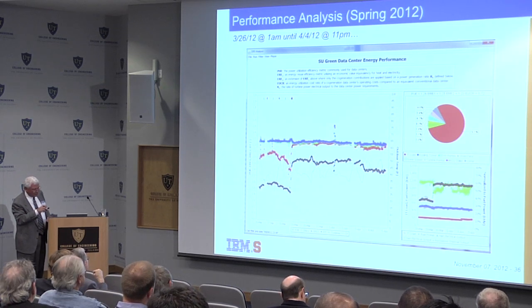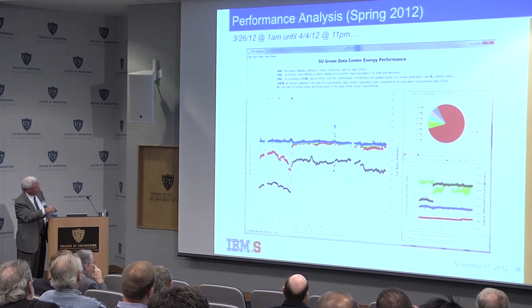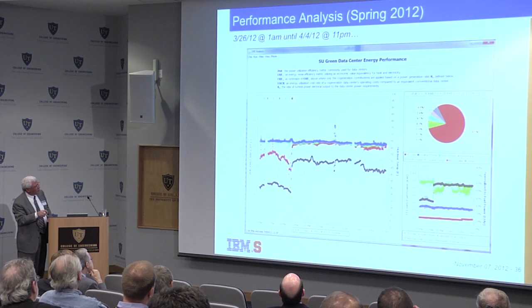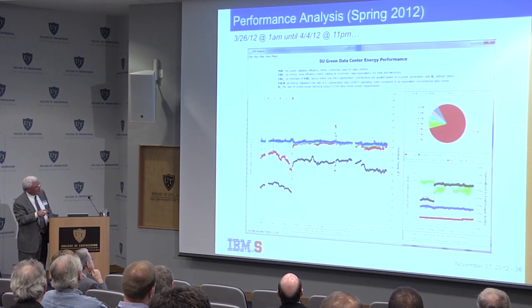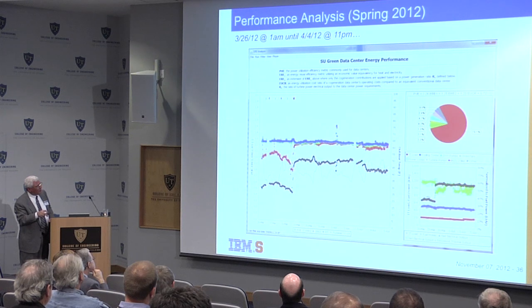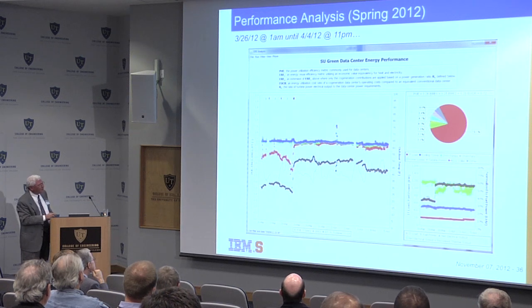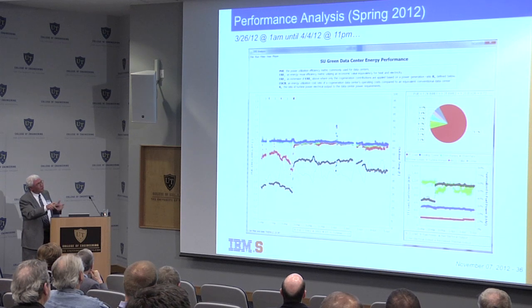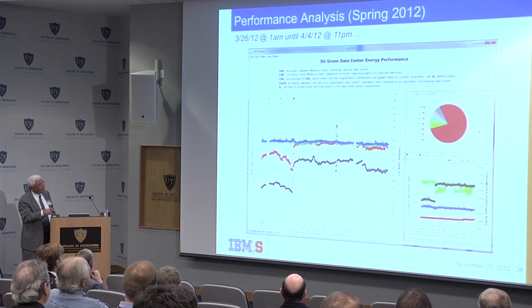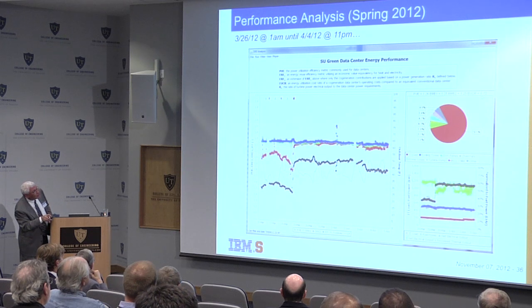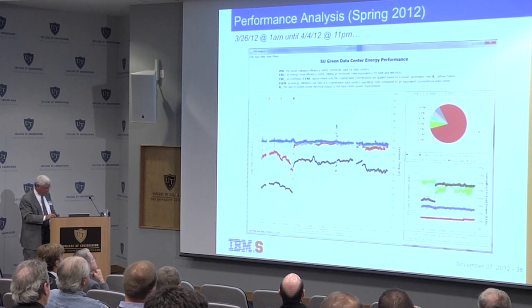You see the ambient temperature here — this is some day near the end of winter. This is the fraction of power provided to the data center coming from the turbines; it's not 100%, close to it but not quite. Then there are pie charts showing the various energy consumers in our data center, and the PUE here ends up being around 1.26.